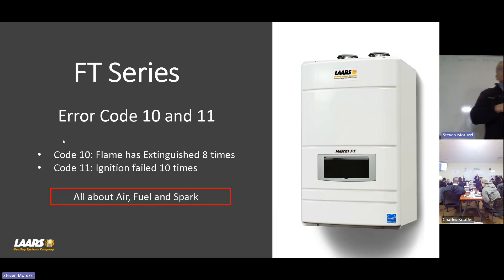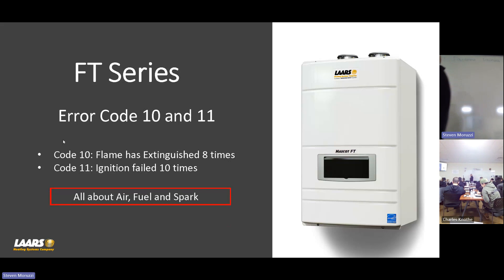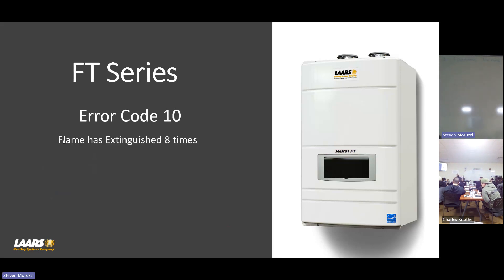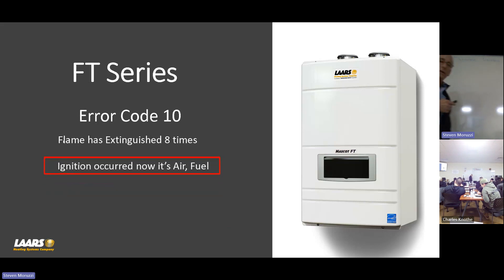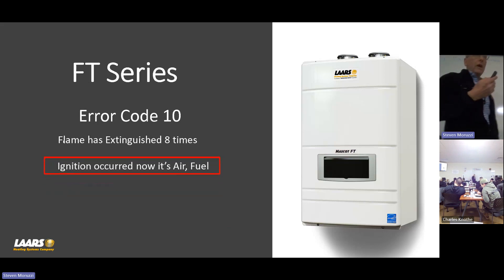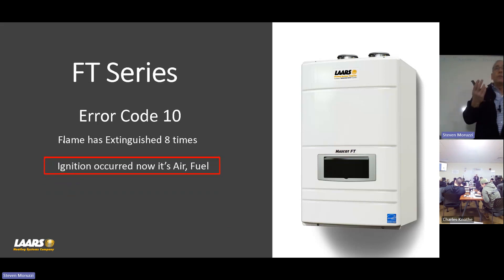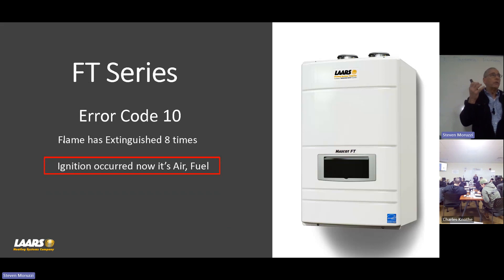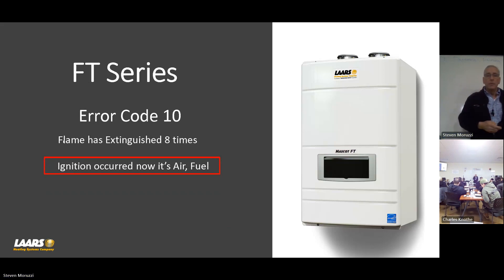What this is, error code 10 and 11 is all about air, gas, spark. Flame has extinguished eight times, that's error code 10. That means that we lit. So what's left? It's air fuel mixture. We actually had spark. Does that make sense?